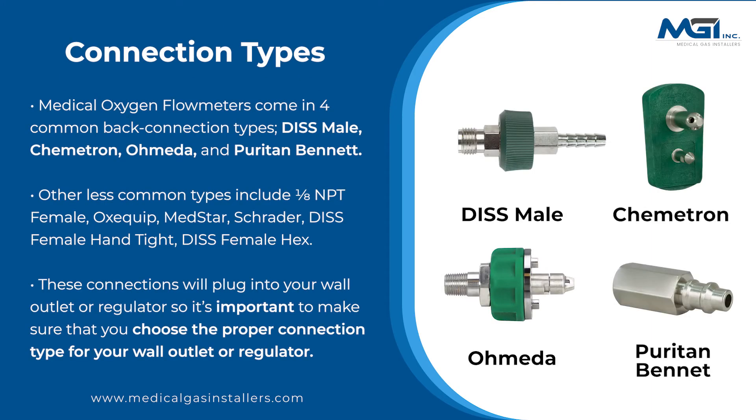Medical oxygen flow meters come in four common back connection types: DISS Male, Chemetron, Omeda, and Puritan Bennett. Other less common types include 1/8th NPT Female, Oxequip, MedStar, Schrader, DISS Female Hand Tight, and DISS Female Hex. These connections plug into your wall outlet or regulator, so it's important to choose the proper connection type for your wall outlet or regulator.